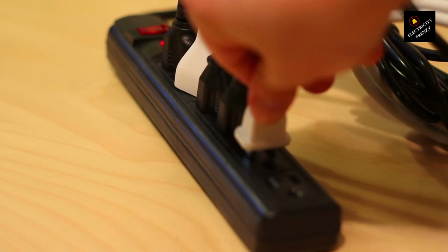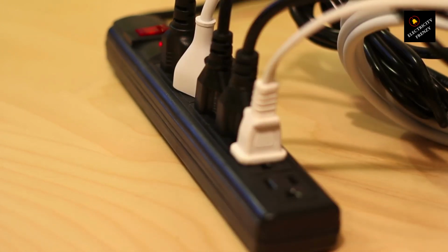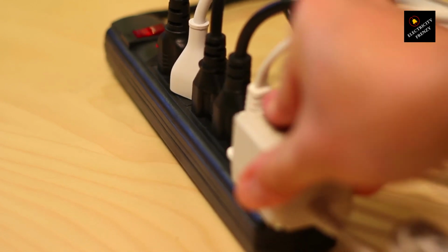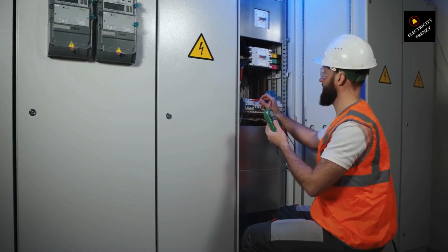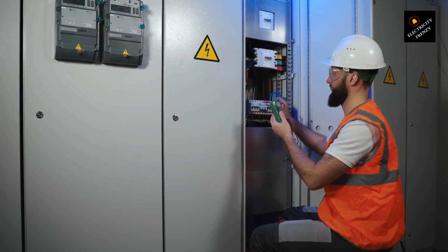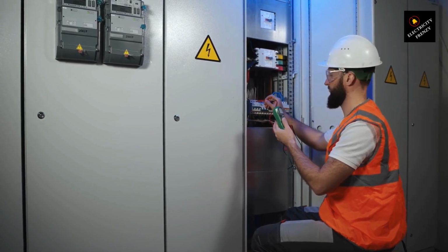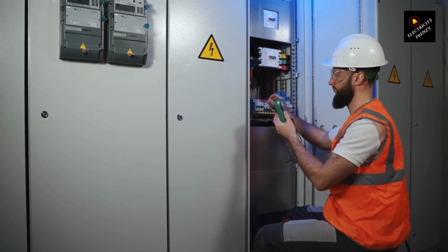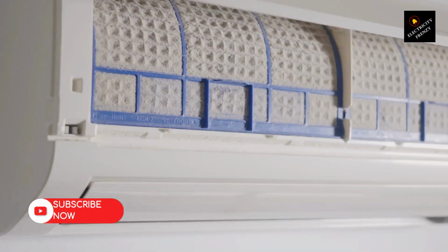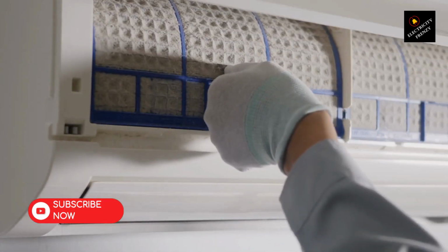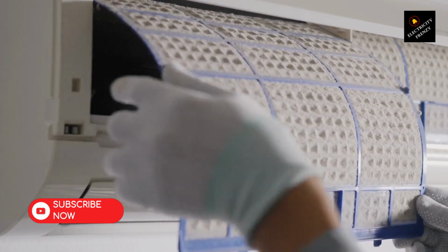Solution to solve this issue: clean or replace the air filter regularly according to the manufacturer's guidelines. Clean the condenser and evaporator coils using a soft brush or vacuum cleaner. If the coils are severely clogged, you may need to call a professional technician for a thorough cleaning. By maintaining clean filters and coils, you can ensure proper airflow and reduce strain on the compressor.